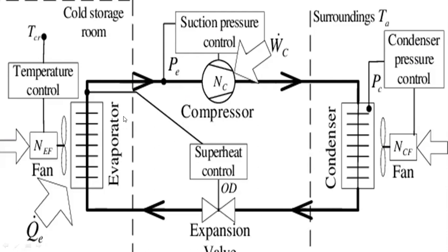You will see the control here. The superheat is controlled by controlling the valve through which the refrigerant is sent inside the evaporator. The extent to which this valve is open decides the superheat of the refrigerant flowing inside, and that thus decides the temperature inside the refrigeration.